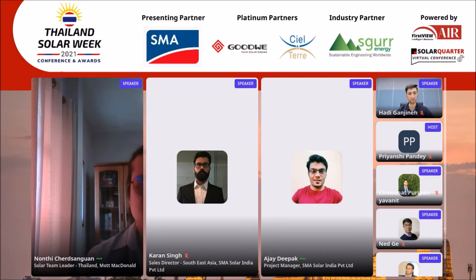trackers in the DC coupled system. And then step by step, we will upgrade the grid or support the grid by means of separate storage applications, for example grid inertia support, which has already been implemented on a trial basis in many countries, in addition to frequency regulation. Grid inertia is one of the new topics. There, the inverter will act as a master. Now it is acting as a slave, listening to the grid. In future, the inverter will create the grid for the system, decide when there is a fault, clear the faults, or support the grid in clearing the faults. So all this will come from the inverters.